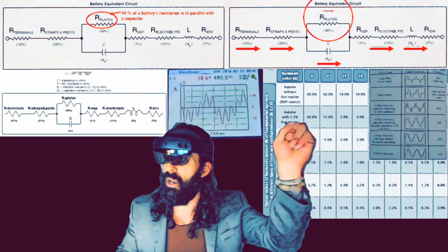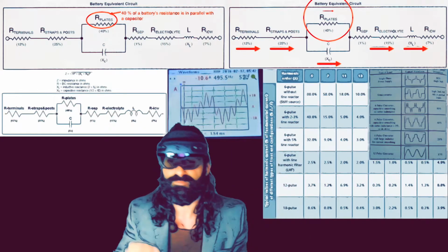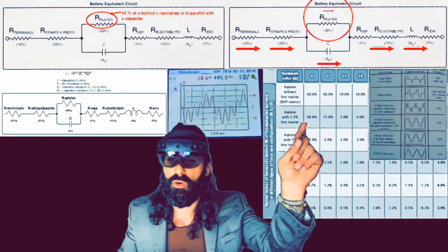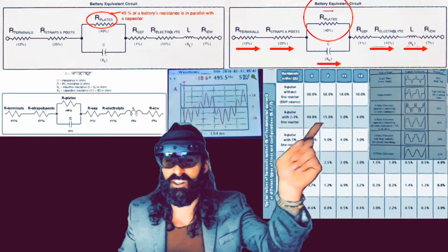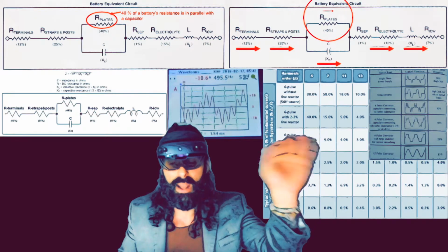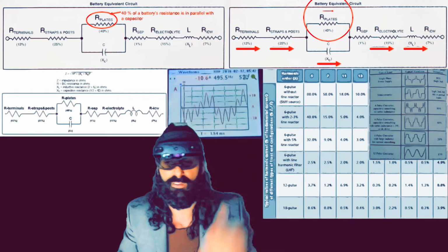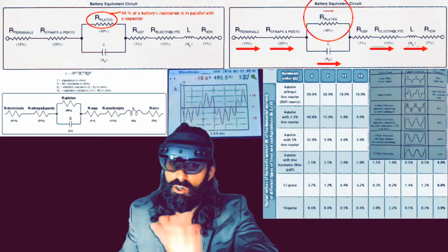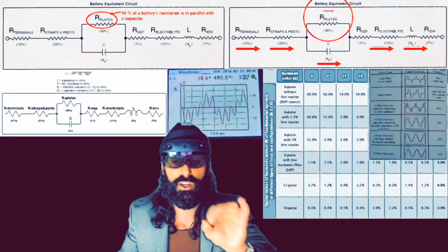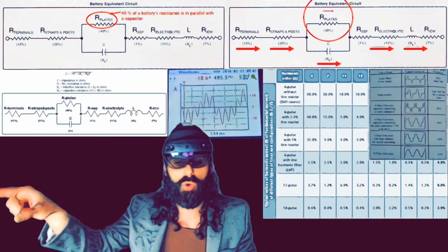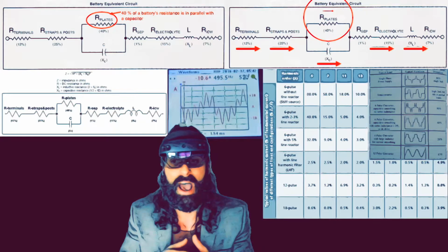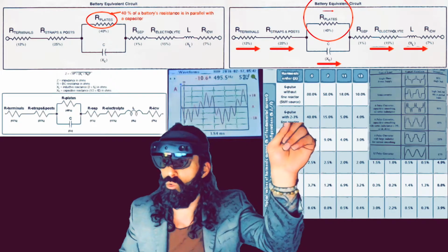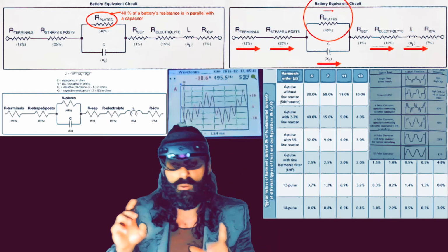So on the other side, up top, you'll see the AC testing methodology, and this is very important. Look at that: the AC signal is going in parallel to that DC resistance. Because of this, depending on the frequency, if it's a bigger battery, say a 1950 amp hour vented lead acid wet cell, and this is ignoring DC resistance entirely, just the noise and the capacitive reactance, you won't see that 40% increase until the battery is open. I've been testing millions of batteries around the world, and this is absolutely true. It doesn't matter what you do at all. And then we talk about noise.